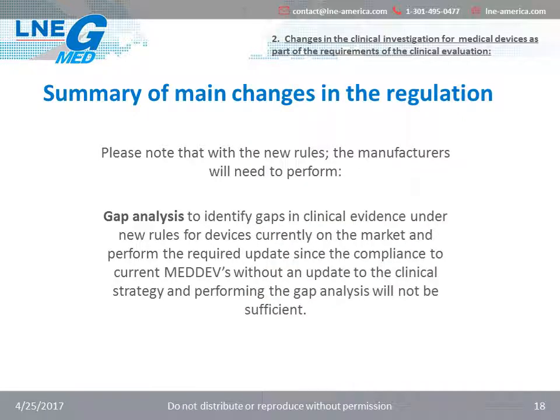Please note that with the new rules, manufacturers will need to perform the following. The first point here is gap analysis. To identify gaps in clinical evidence under new rules for devices currently on the market and perform the required update, since the compliance to current MedDevs without an update to the clinical strategy and performing the gap analysis will not be sufficient.